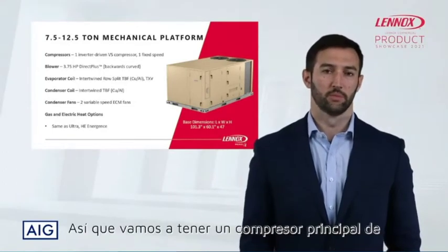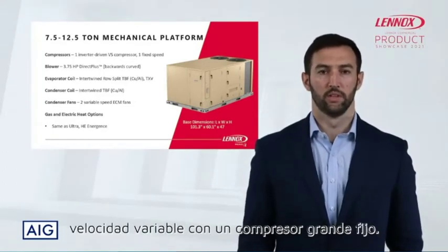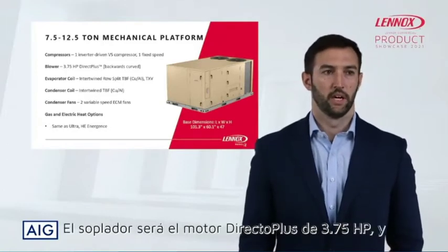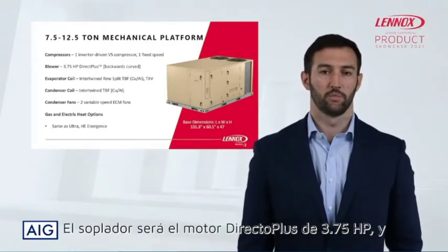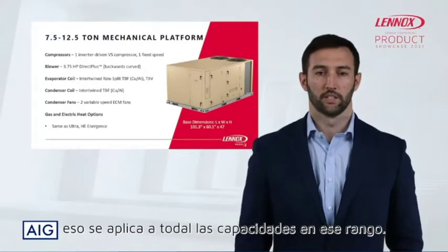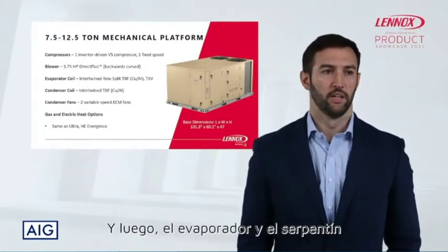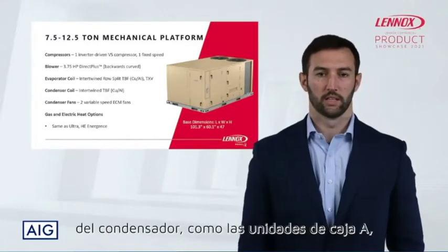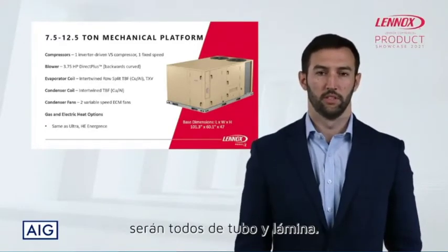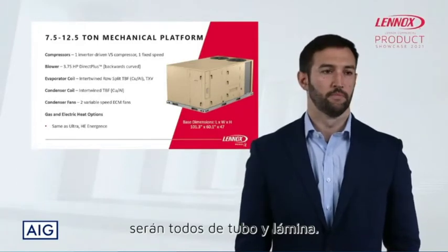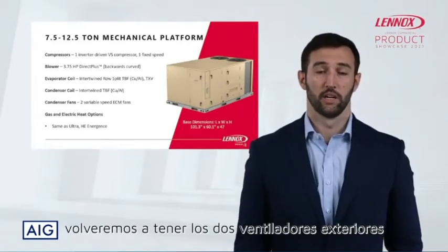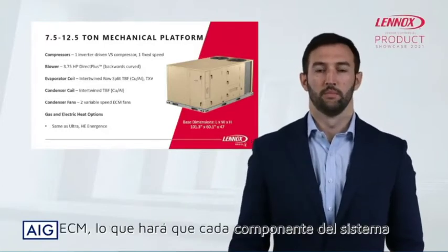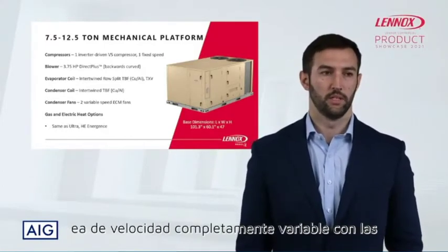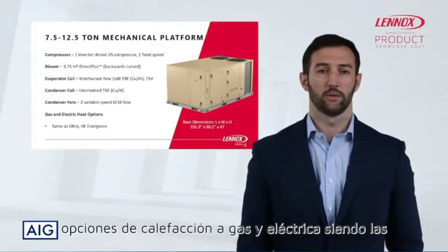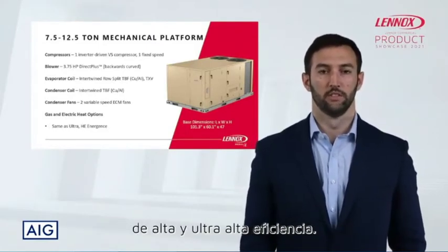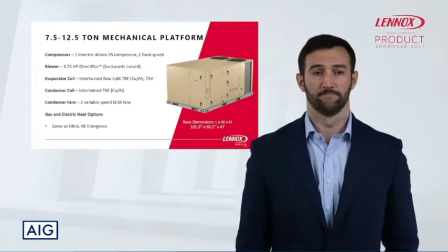So we're going to have a lead variable speed compressor with one fixed speed lag compressor. The blower is going to be the 3.75 horsepower DirectPlus motor. And that's going to be for all of the tonnages in that range. And then the evaporator and condenser coil, like the A-box units, will be all tube and fin coils. And so when you look at the condenser fans, we're going to have the two ECM outdoor fans, again making every component in the system fully variable speed, with the gas and electric heat options being the same as Energen's high efficiency and ultra high efficiency today.